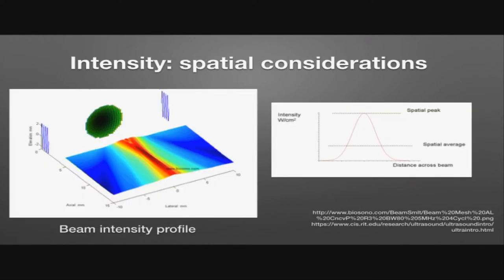Considering the spatial aspects of intensity: a beam intensity profile in three dimensions shows the highest intensity in the central portion of the wave. In a cross-section with distance across the beam on the x-axis and intensity in watts per centimeter squared on the y-axis, the centre of the beam has the highest intensity, falling off at the peripheries. There are two values: SP — spatial peak — and SA — spatial average. Spatial average is the average intensity across the entire cross-section at a specific depth. Spatial peak is the point of greatest intensity, typically at the central axis or at the focus point.